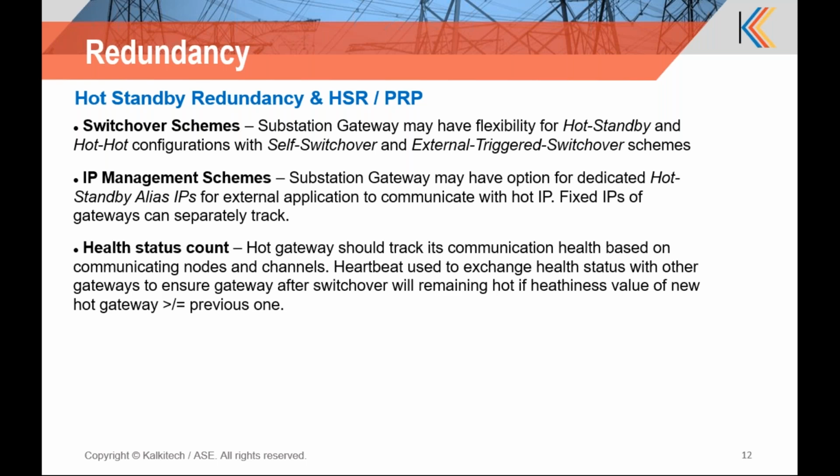Whenever the standby gateway turns hot, it compares the present healthiness status with the previous hot gateway's healthiness status. If the present gateway has better or equal health, it will continue in the hot status itself.